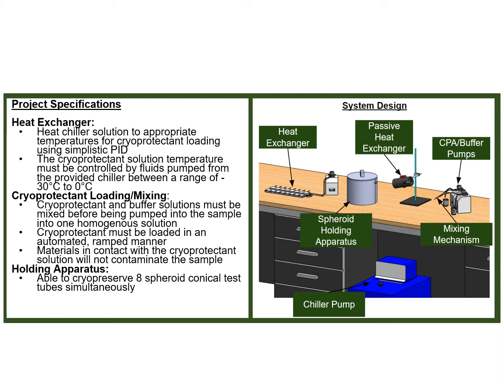The cryoprotectant loading and mixing system is required for the cryoprotectant and buffer solutions to be mixed before entering the sample as one homogeneous solution, loaded in an automated, ramped manner. The material in contact with the cryoprotectant solution must not contaminate the sample.